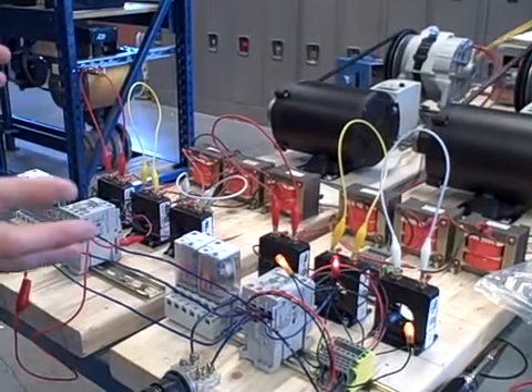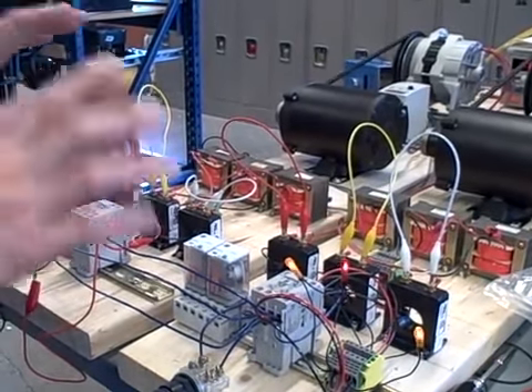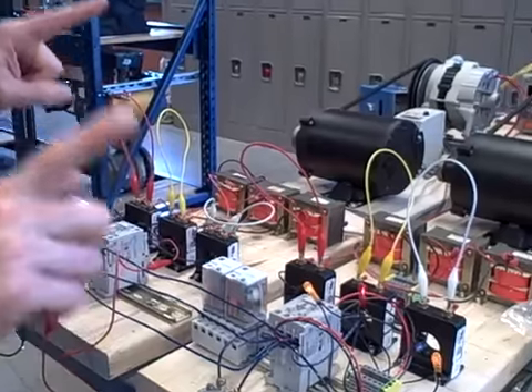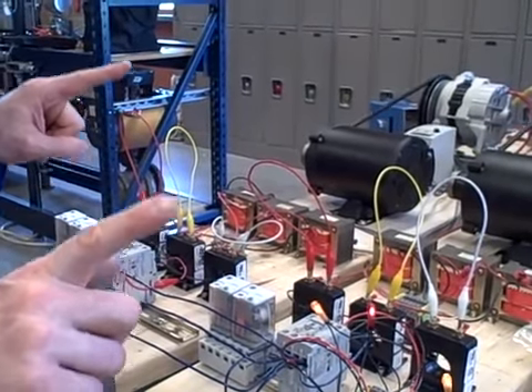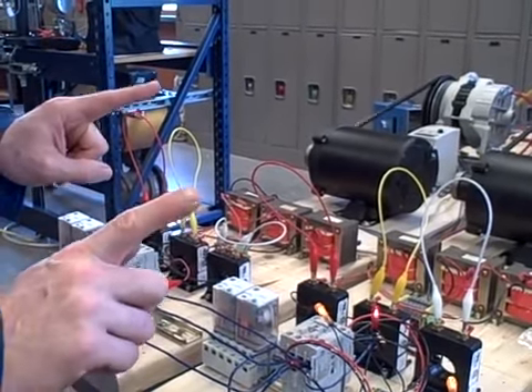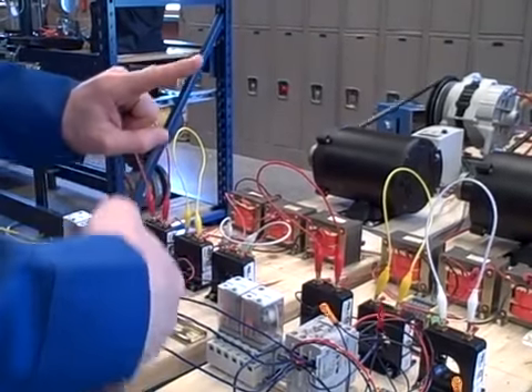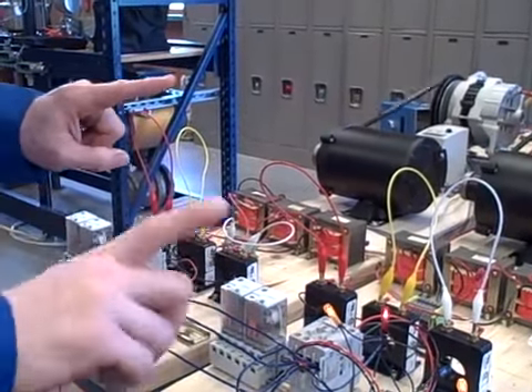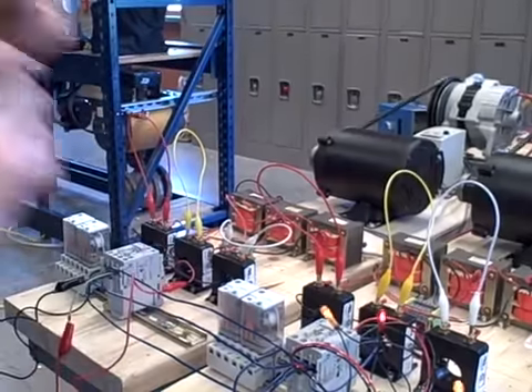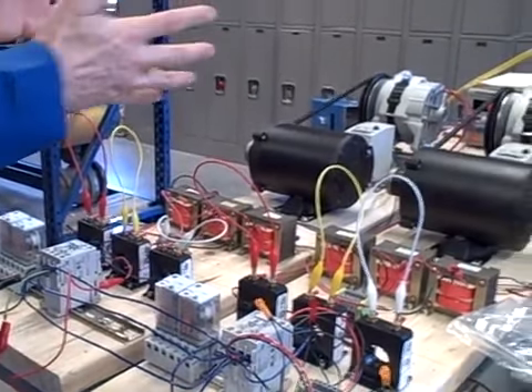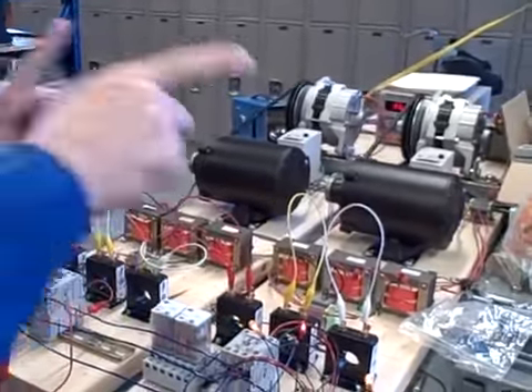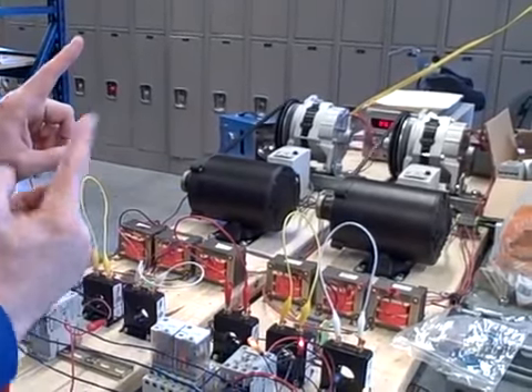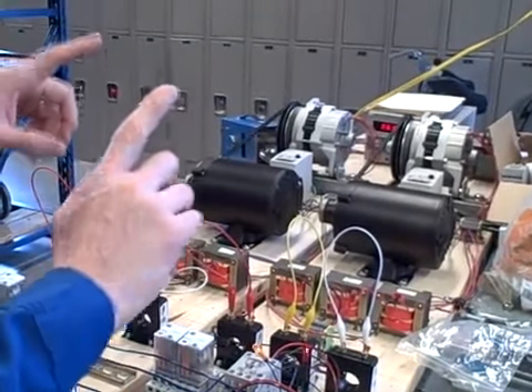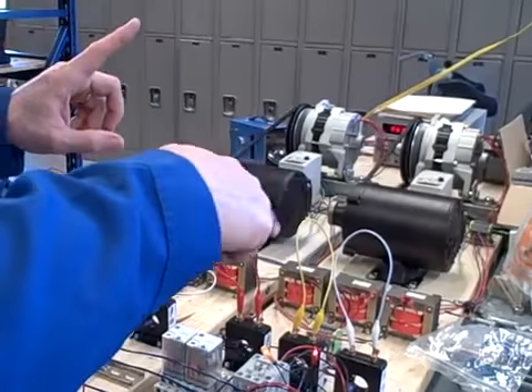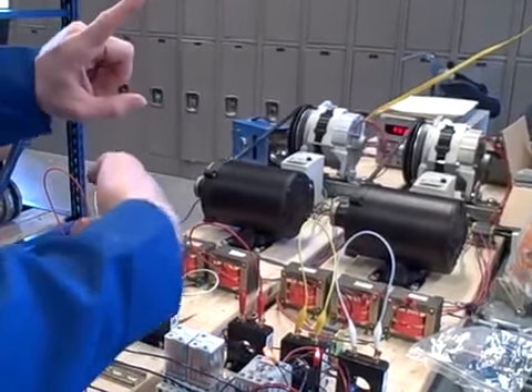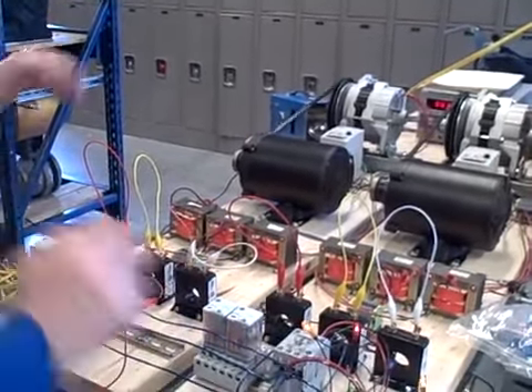Because one's going slower than the other, they're continually falling in and out of sync with each other. You can think of this simplistically as being like two batteries being connected in parallel. If we wish to connect two batteries in parallel, they must be of the same voltage and the same polarity. If we get one battery backwards, bad news. Hook them up together, you get a short circuit. So you want to hook up batteries together in parallel with like polarities. Well, AC generators are kind of like batteries that are spinning around. So as they spin around and come in phase with each other, they have the same polarity. But if you let one of them spin at a different speed until it's opposite, they've got opposite polarities. If you try to close that breaker then, bad news, short circuit.